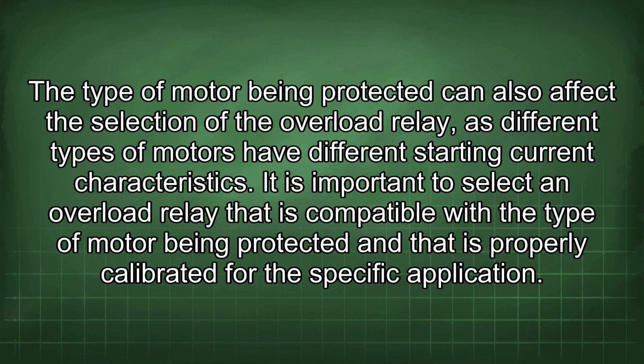The type of motor being protected can also affect the selection of the overload relay, as different types of motors have different starting current characteristics. It is important to select an overload relay that is compatible with the type of motor being protected and that is properly calibrated for the specific application.